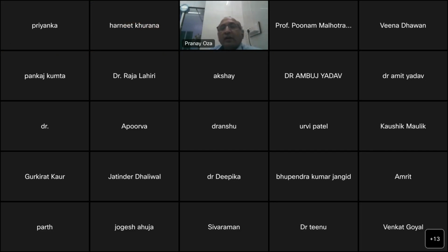Meanwhile, there's one question from the delegates. If a person is not able to feed enterally, what TPN should we use? Usually we avoid using the lipid-based one. We just give them the essential amino acids and the dextrose. But with the PMP oxygenator, we can use even the lipid-based one. Definitely we try to avoid it as far as possible, because silicone oxygenators and hollow fiber oxygenators have a lot of issues with lipid-based drugs and lipid-based parenteral feeds. So we usually try to avoid that.